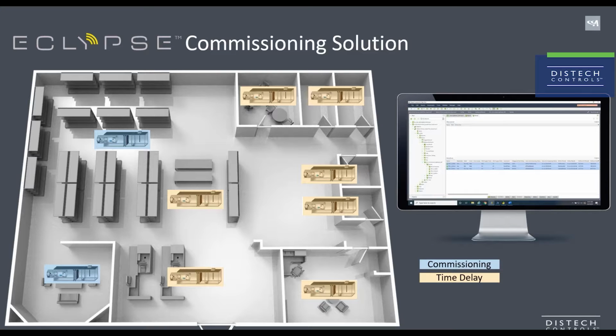You can see from this image that 2 of the 9 VAVs are in an active commissioning state, while the 7 others are in a time delay state, waiting their turn to begin the commissioning process. Once the time delay for the second group has elapsed, they'll begin their commissioning process. You can see that the first 2 VAVs have passed. At this time, the result will be logged and they will resume their normal EC-gfx program sequence. The second group of devices are now in an active commissioning state. The 5 others are still waiting their turn as their time delays have not elapsed. This intelligent staggering will continue until the last group of VAVs complete their commissioning process.